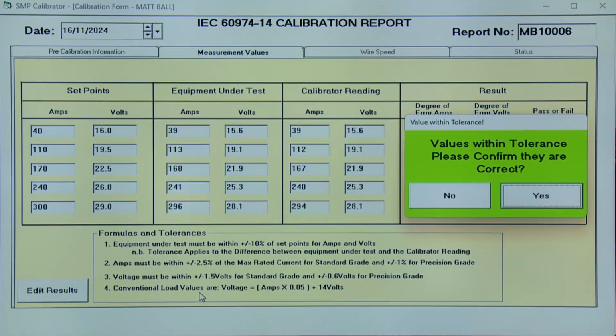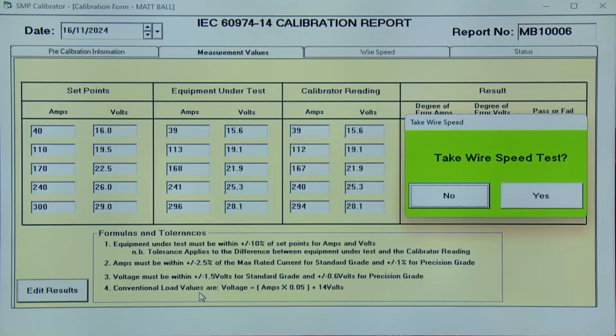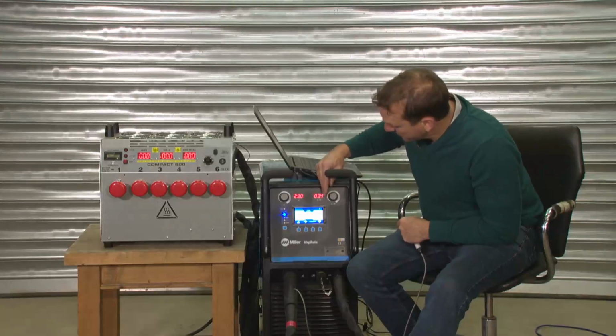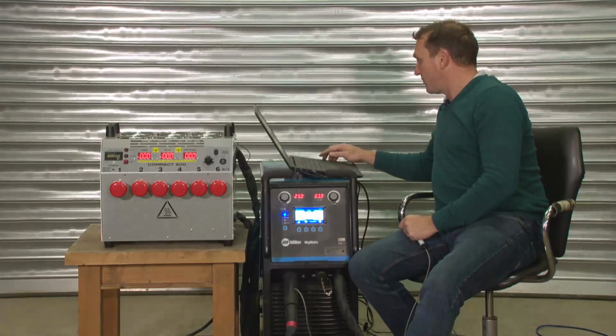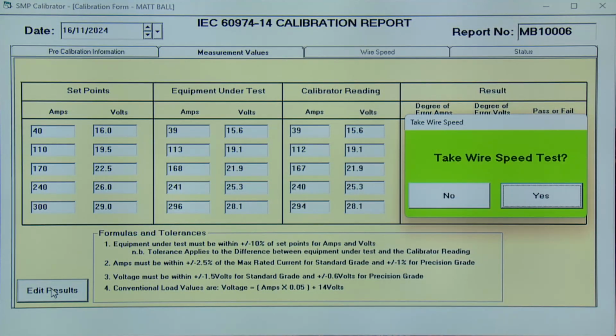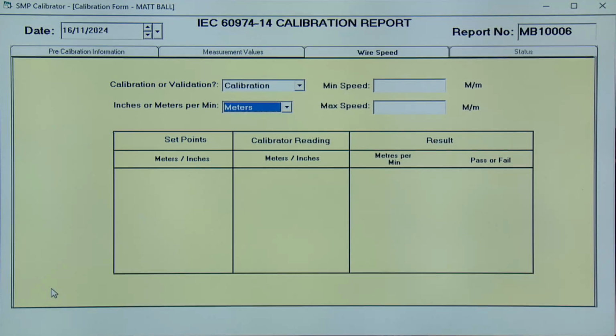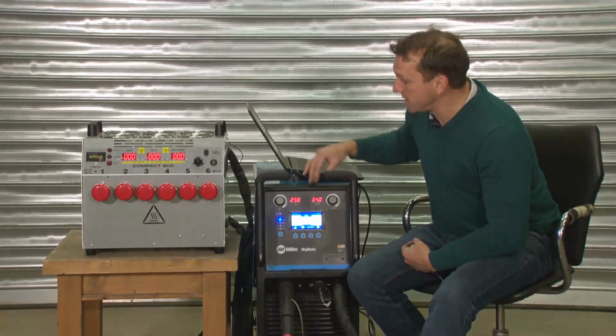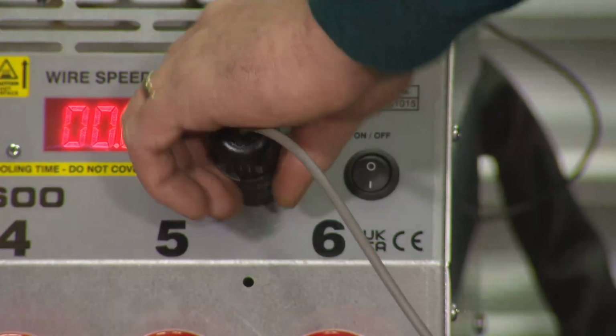Once that final reading's been taken, we confirm all our readings are correct and we're asked, do we want to take wire speed? We have wire speed adjustment on this one, so yes, we're going to take wire speed. We're going to do the calibration in meters per minute with our minimum speed at 4 meters per minute. And our maximum at 20 meters per minute. Again, the program automatically selects your readings in between. So now we've got our minimum reading set, we'll plug in the tacho unit, ready to take the wire feed readings.